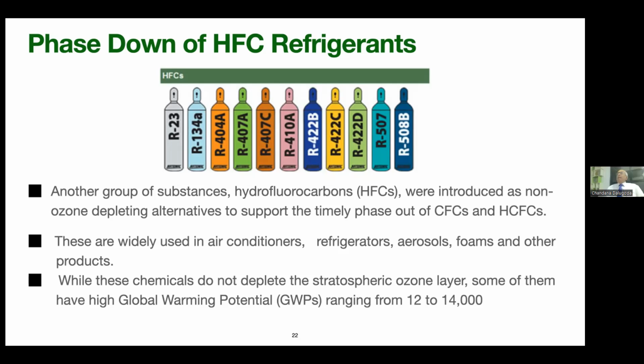That is, the 400 series is a blend, zeotropic blends. One common gas is 407C. It is a replacement gas for R22, a drop-in replacement. On the other hand, there is a very new refrigerant, 410A, for air conditioners. Now that is also being questioned and there are attempts to remove it. So HFCs are going to be removed. The reason: these chemicals do not deplete the atmospheric ozone layer, but some of them have high global warming potential. So that is the problem.